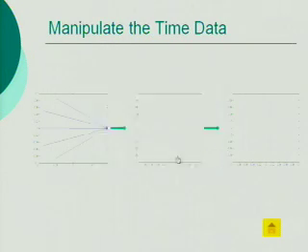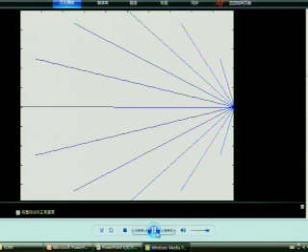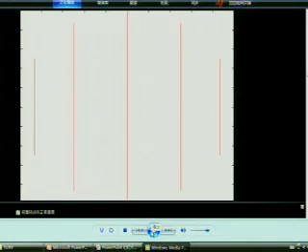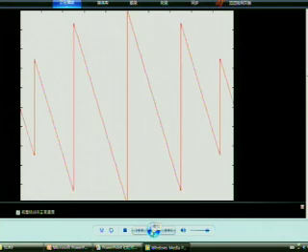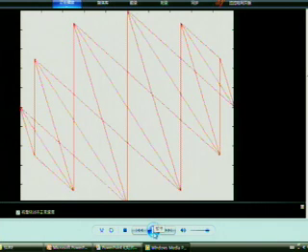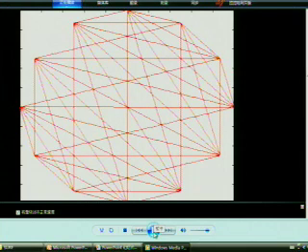As a reminder, we store data so that the time of paths from the first transmitter goes to the first row, the second transmitter to the second row, and so on. What we want instead is for the first row to contain the time of paths making a zero degree angle with the y-axis, the second row for paths making a 15 degree angle, and so on. It contains all the same data — it's just reallocated.